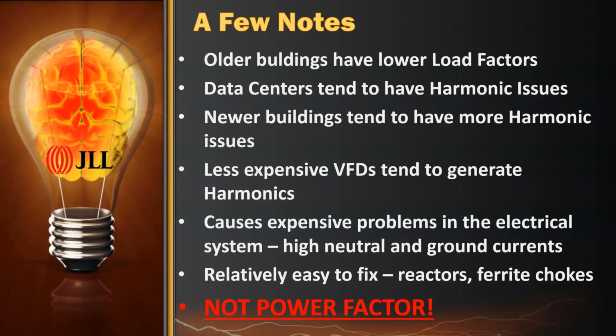We're going to talk a little bit later on about neutral and ground currents, but neutral currents tend to really overheat transformers. Ground currents can actually burn out the grounding rod or grounding grid in the building. That's a real bad problem when that occurs. Very expensive to fix, and it creates a condition, an ungrounded electrical system, that is actually quite dangerous. It's relatively easy to fix, though. You can use input line reactors or ferrite chokes. I'll talk about them in a minute. There's that warning again: not power factor.